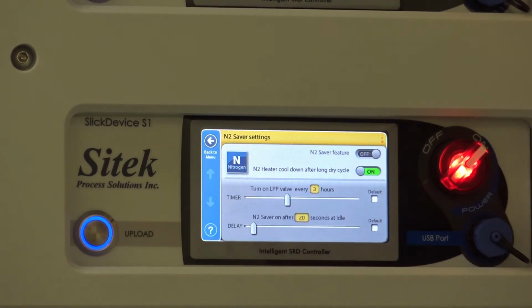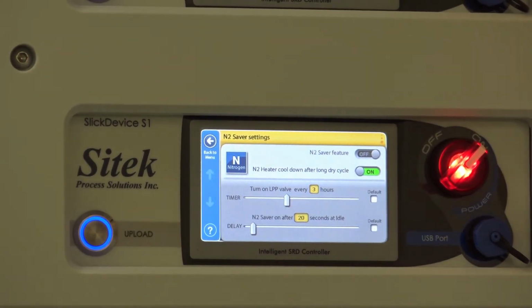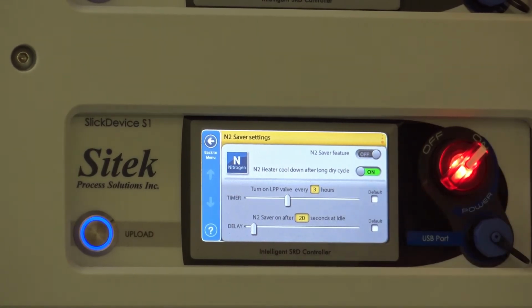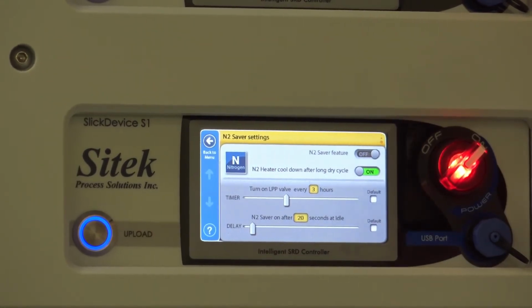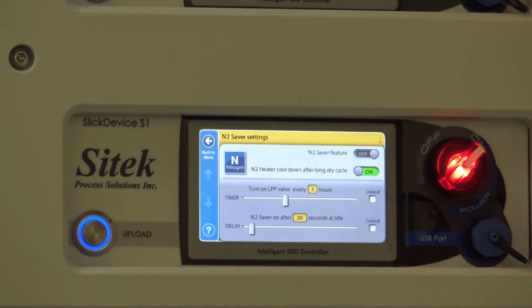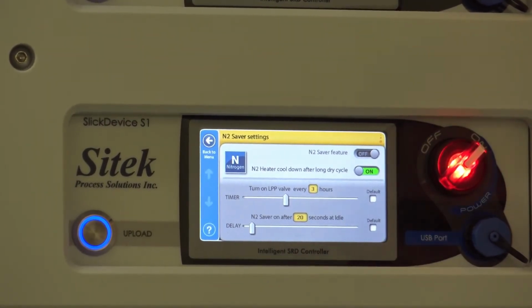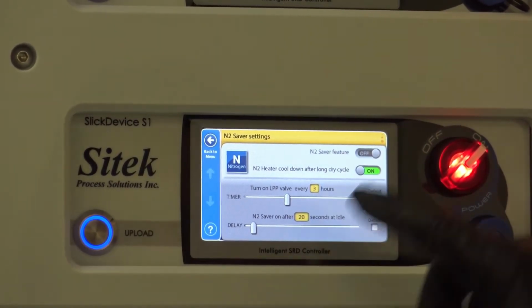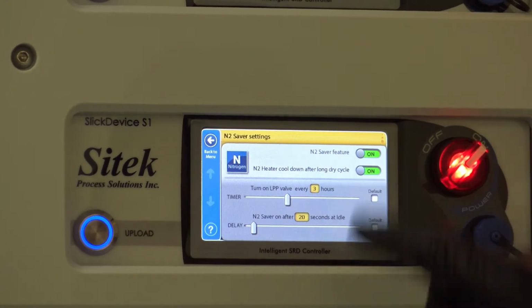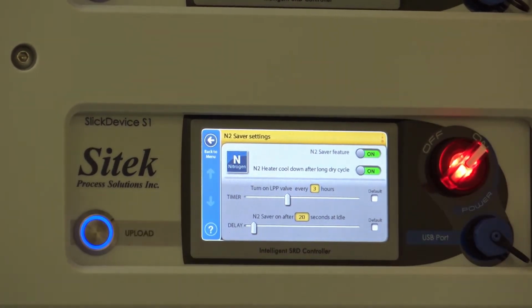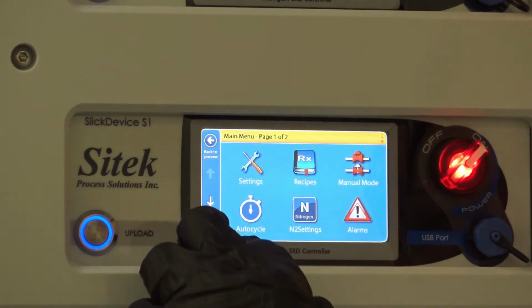The reason is that the N2 heater on a long dry cycle gets very hot. And we've done studies that 20 seconds wouldn't be enough to really cool it down. So we have a pre-programmed extended time that if you run a process that's more than 5 minutes of dry, actually more than 9 minutes total, the auto cool, if you have it on, automatically goes into effect. If you don't want to use the N2 saver, it's on or off. I'm going to turn it on because right now it's off, and that's all you have to do. And I'll show you how that works in a second.